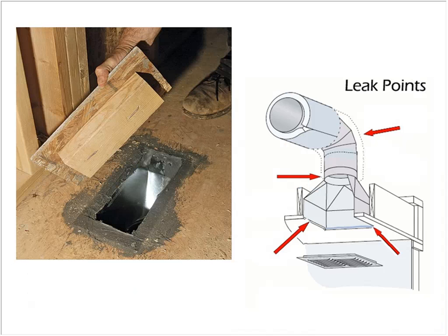Really, this air sealing is important because heating and cooling systems are going to be closer to being properly sized instead of being oversized. Oversizing is oftentimes compensating for these types of leaks in the duct, because if it's a well-sized system, it's going to be much smaller based on the heating and cooling loads of a well-insulated and air-sealed home. So it's more important to get that conditioned air to the living space which is occupied, rather than leak into wall cavities or floor cavities of a home where it doesn't benefit the occupant.